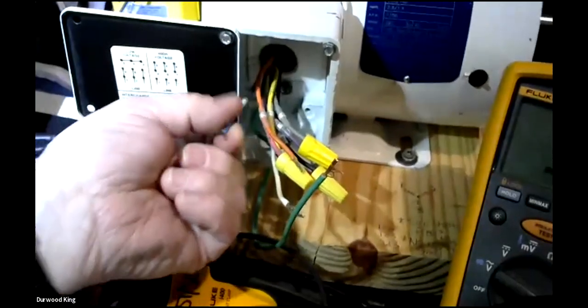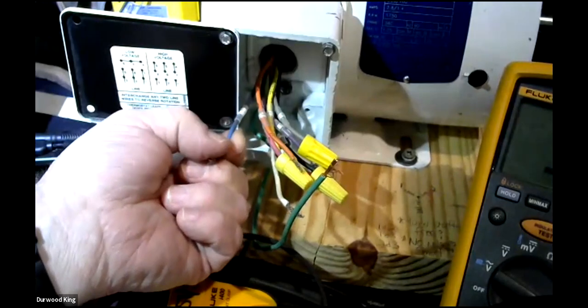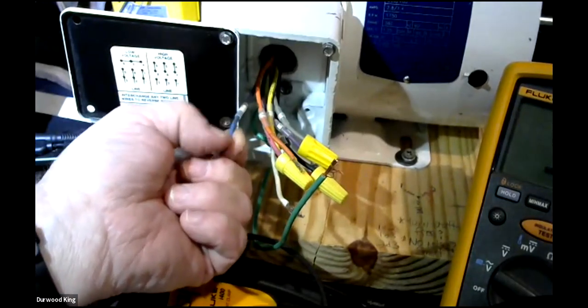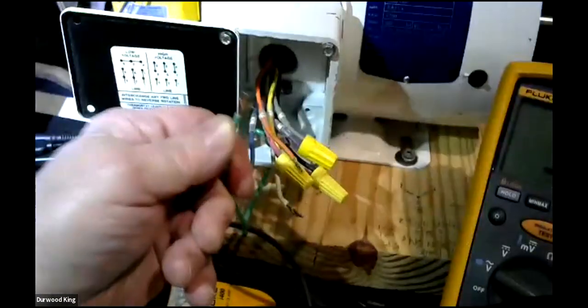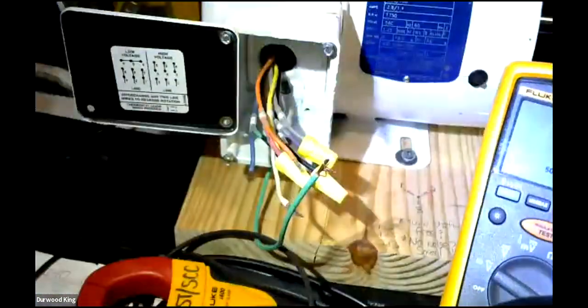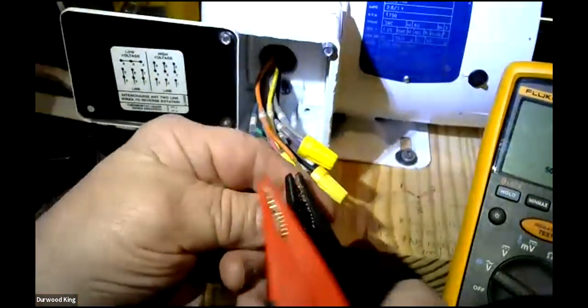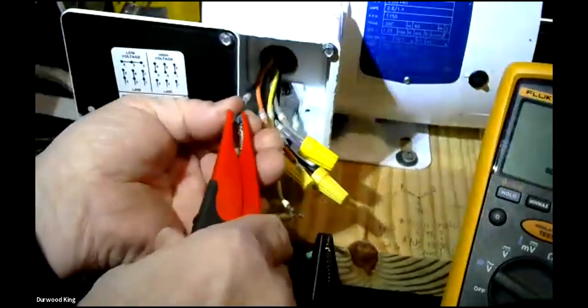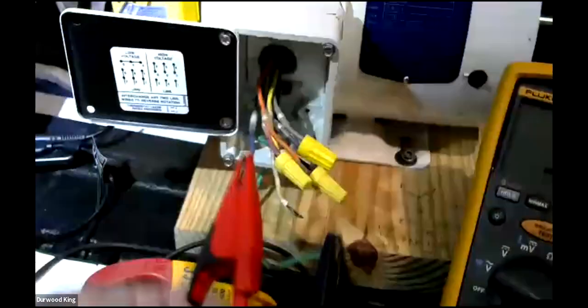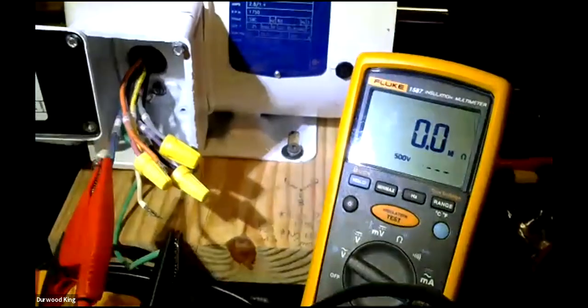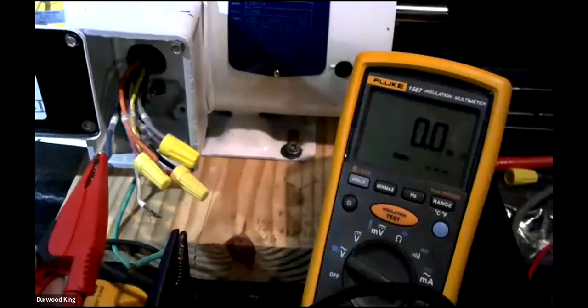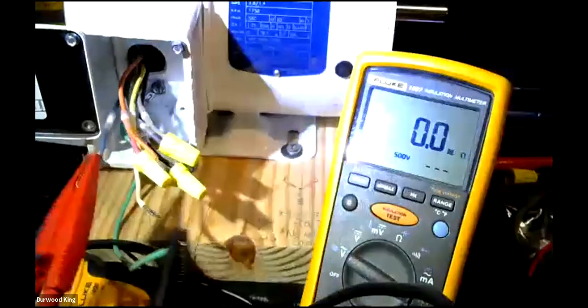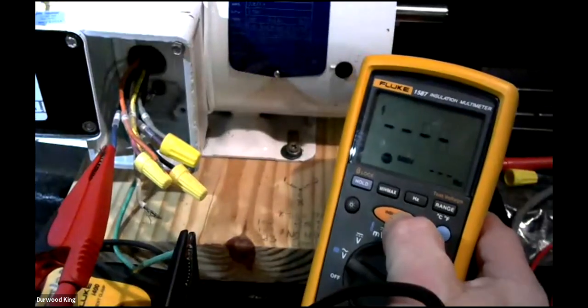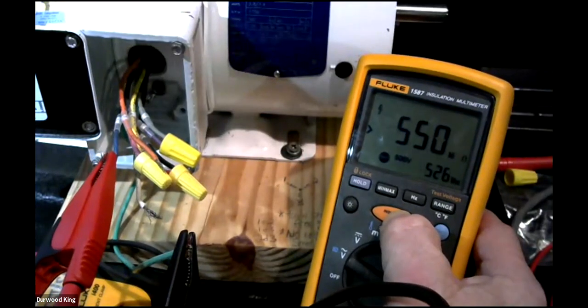What it's doing is detecting if you have any leakage current from the insulation in that wire, if it's cracked or melted inside the motor. It's going to tell you, is there any current leaking from this getting on the frame and coming back on that ground wire? It's detecting leakage current in there that's going to ground. So here we go. We're going to ground, and we're going to go to line 1. We have those two hooked up, and we go back to here, and I hit the test button, or just for your sake, I can hit it up here and watch. Just watch it. See that? And what does it say? 550. Greater than 550 meg, so it's actually good.